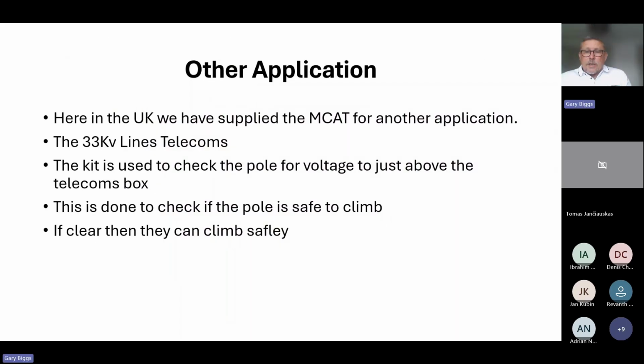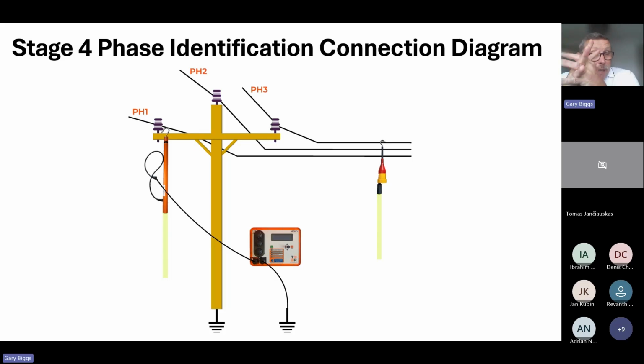So that, essentially, ladies and gentlemen, is the way in which the MCAT is used. It's relatively simplistic, and that's the whole idea of the instrument, to make that job very, very easy. We're looking at the cross member, we're checking if there's a voltage there. If we find a voltage and the voltage is below 2.7 kV, we would then check the potential current that's there at that cross member, and if there is a leaky insulator, we then use that wireless probe to identify the insulators.